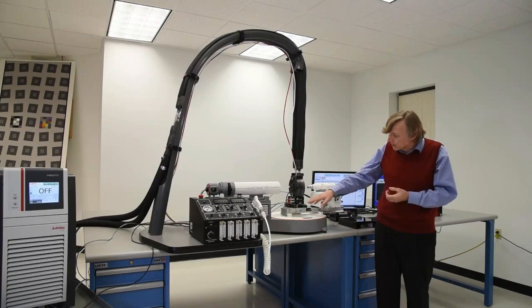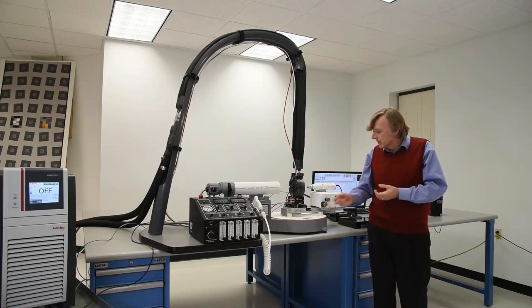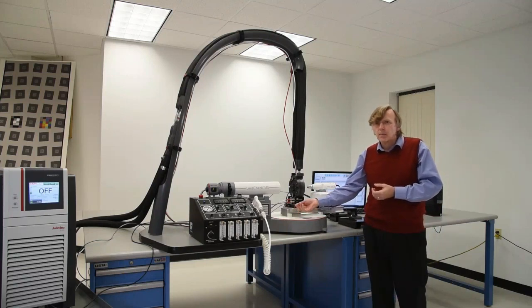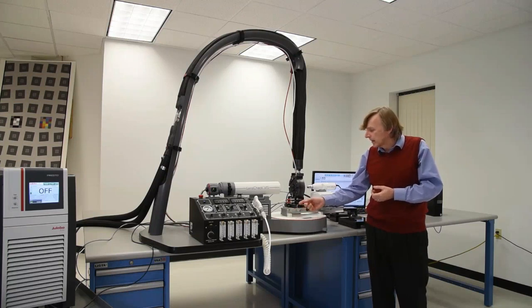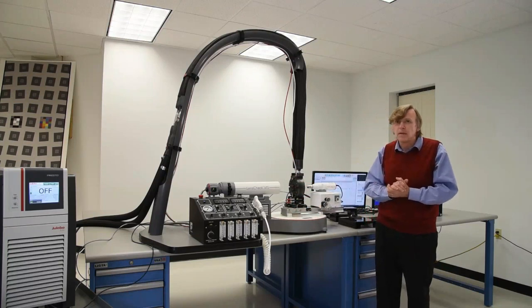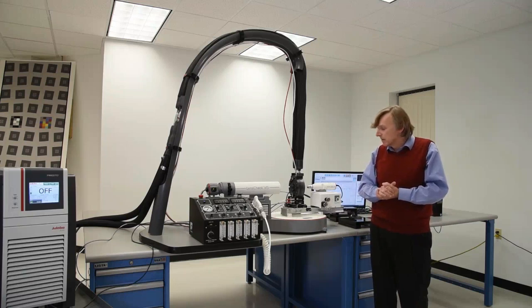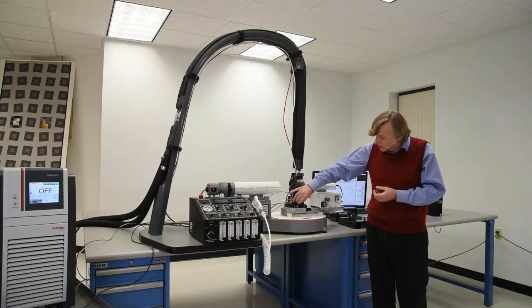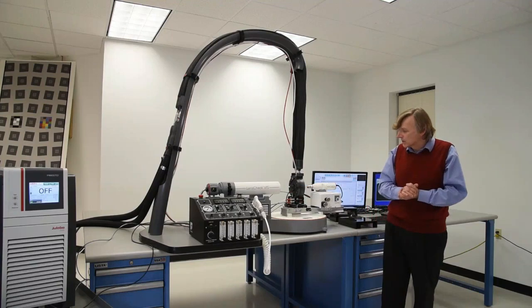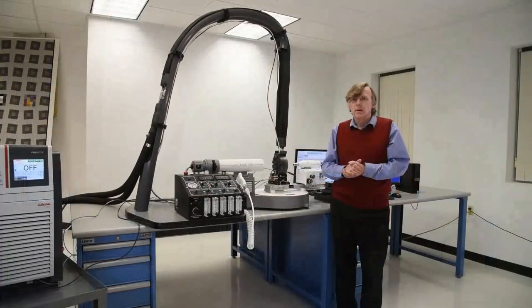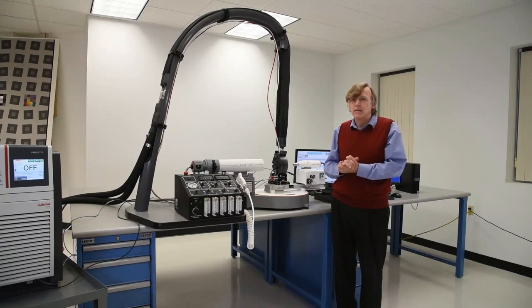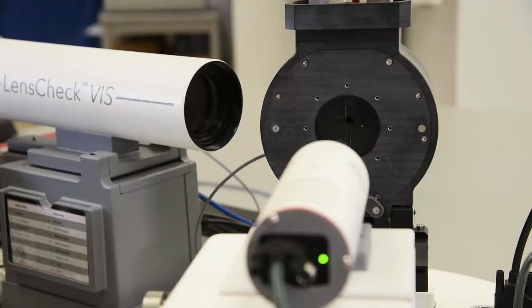We can see how the chamber mounts to the optical rail in place of the usual lens mount. The pitch and yaw controls that are required to align the lens to the collimated beam are incorporated into the base of the unit. The operator locks those controls with this knob after making the necessary adjustments. Although we cannot place an optical window in the convergent light path, it makes sense to close the chamber while the lens is undergoing a change in temperature, and to open it only for the time actually needed to make a measurement. This is achieved through a mechanical shutter, which we see opening and closing.